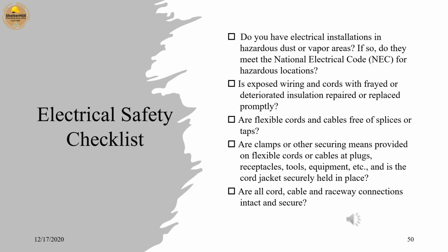Do you have electrical installations in hazardous dust or vapor areas? If so, do they meet the National Electrical Code, NEC, for hazardous locations? Is exposed wiring and cords with frayed or deteriorated insulation repaired or replaced promptly? Are flexible cords and cables free of splices or taps? Are clamps or other securing means provided on flexible cords or cables at plugs, receptacles, tools, equipment, etc., and is the cord jacket securely held in place? Are all cord, cable, and raceway connections intact and secure?